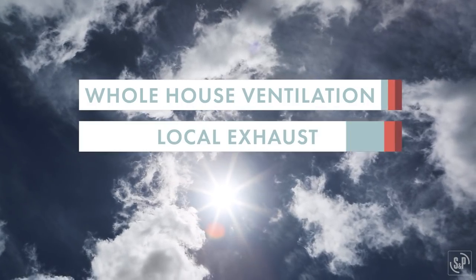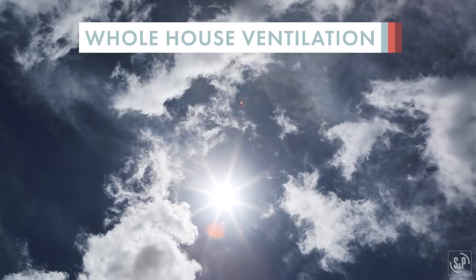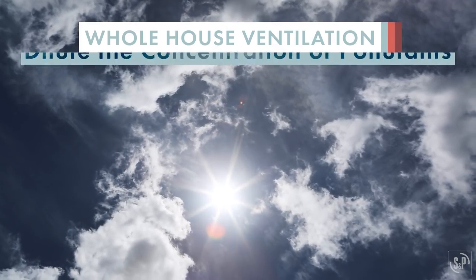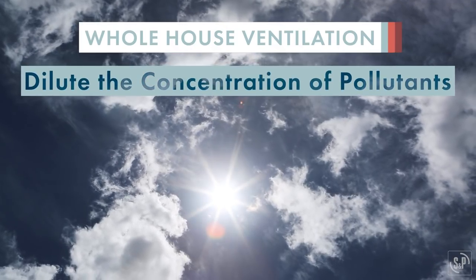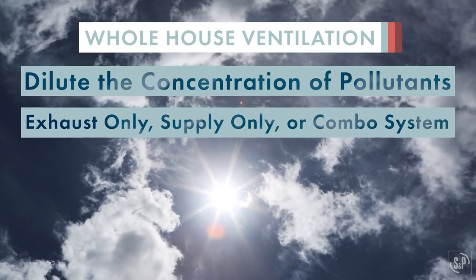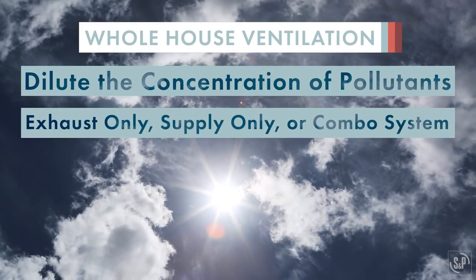There are two basic requirements: whole house ventilation and local exhaust. The first basic requirement, whole house ventilation, is intended to dilute the concentration of pollutants through either an exhaust only, supply only, or combo system.